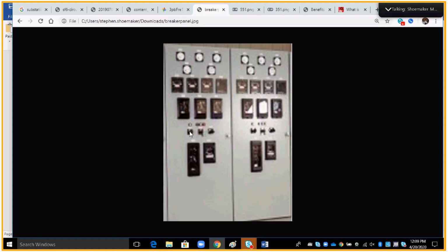This is going to show to the off position. This is going to be lit up. Right when SCADA, if I call SCADA and tell them, well, I need to give up my hotline work permit, a little motor in here turns it back on. This light goes out. So that's an OSHA requirement. You need to have something visual on your breaker to show that you have the reclosing relay turned off.